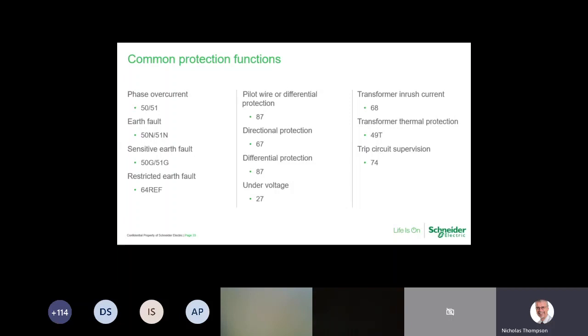And then we start to look at pilot wire protection, directional protection, where you might be concerned about faults running in not just one direction, but maybe the other one. Differential protection is where you're on transformers or generators or motors, where you're looking for a fault inside the transformer. So for transformer differential protection, it's one relay, but it's two sets of CTs. So you have a set of CTs on the primary side, and you have a set of CTs on the secondary side, and the software within the relay is looking for an imbalance of what's going in and what's going out.